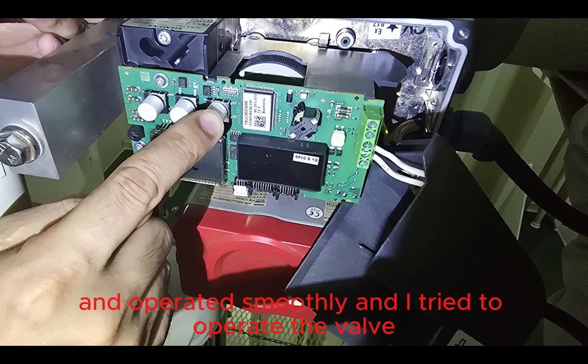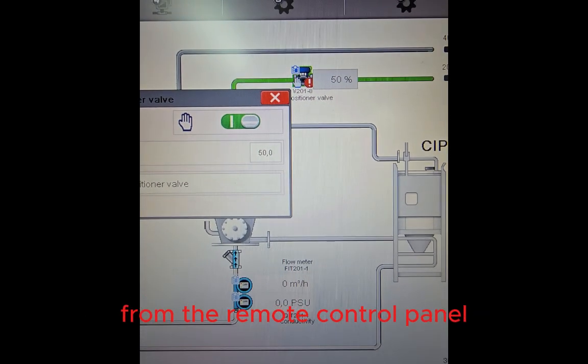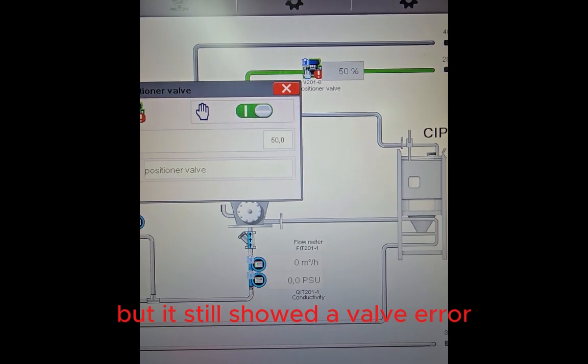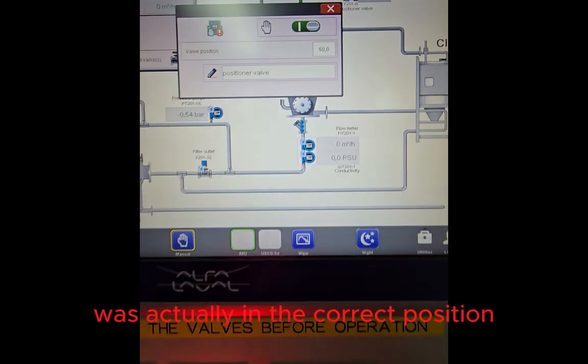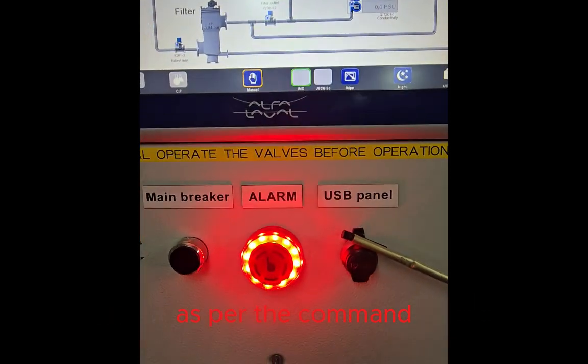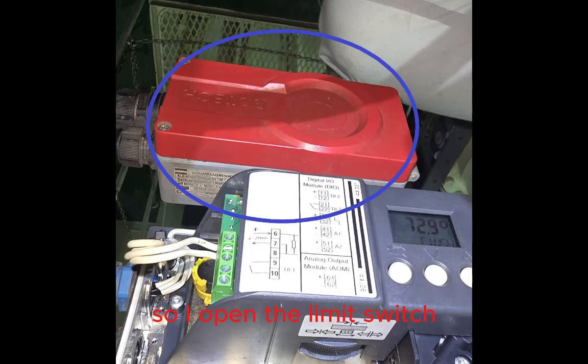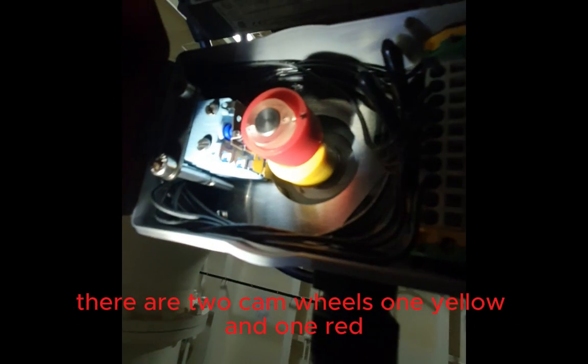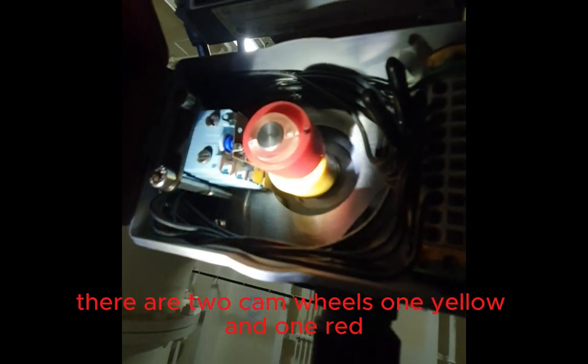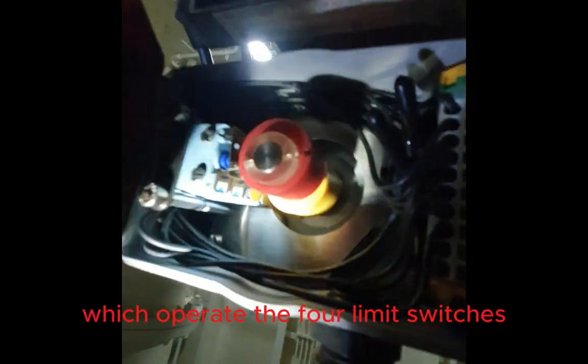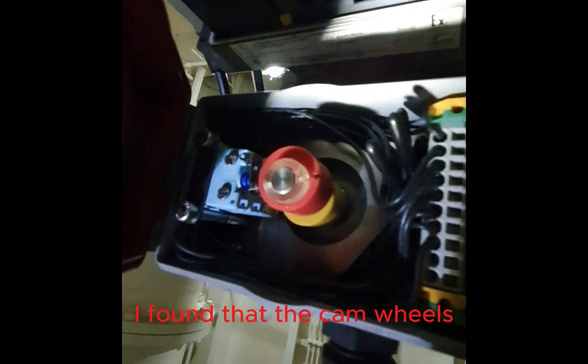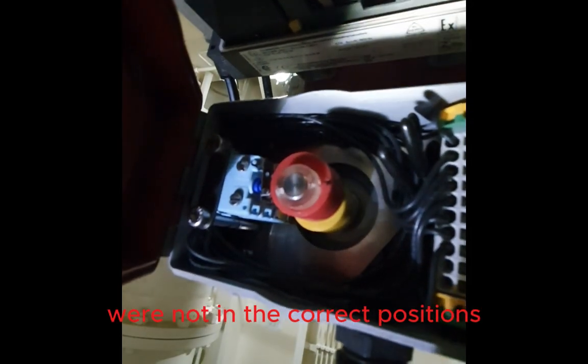Then I tried to operate the valve from the remote control panel, but it still showed a valve error, even though the valve was actually in the correct position as per the command. So I opened the limit switch box located under the positioner. Inside there are two cam wheels, one yellow and one red, which operate the 4 limit switches. I found that the cam wheels were not in the correct positions.